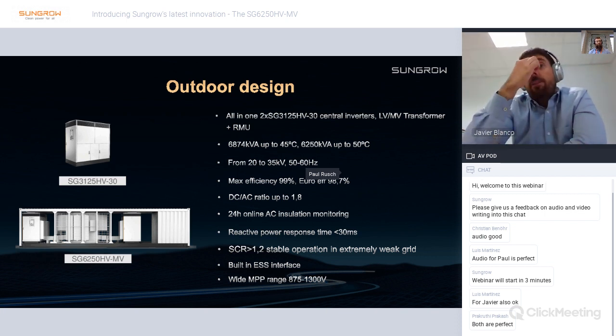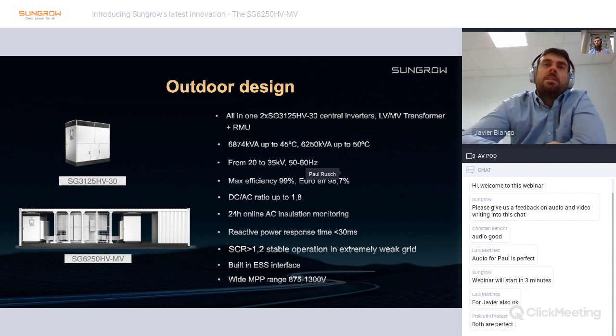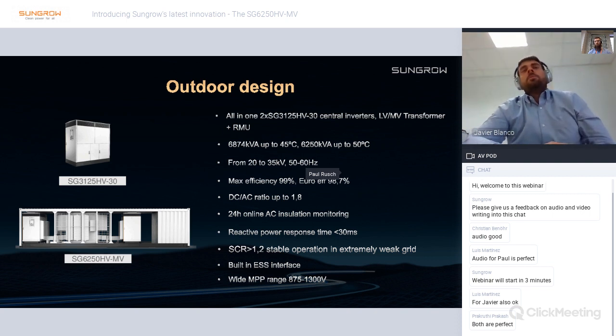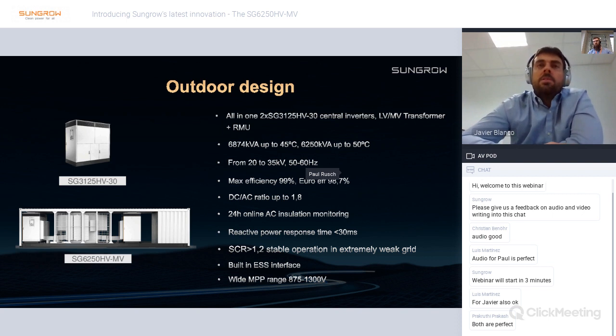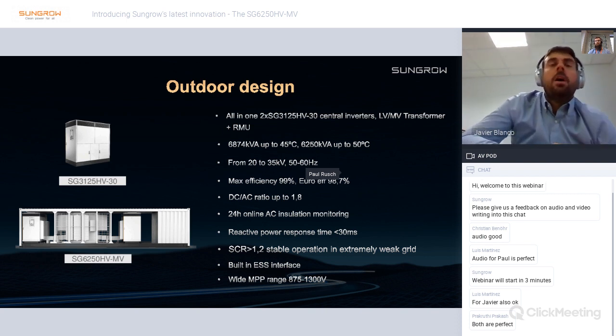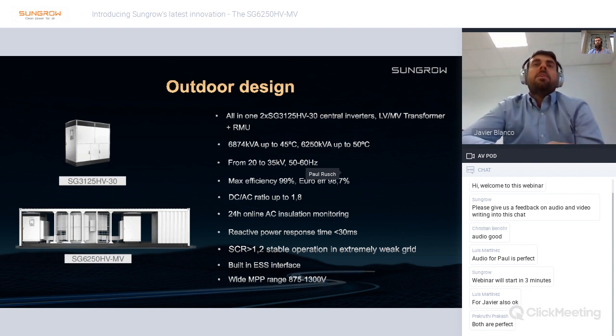The rated apparent power of this MV station is 6,874 kVA up to 45 degrees. In the range from 45 to 50 degrees, there is a small derating down to 6,250 kVA at 50 degrees, and the rating between 45 and 50 degrees is linear between these two values. It is able to be connected to an AC grid in the range from 20 to 35 kV, of course being able to operate at 50 or 60 Hz.